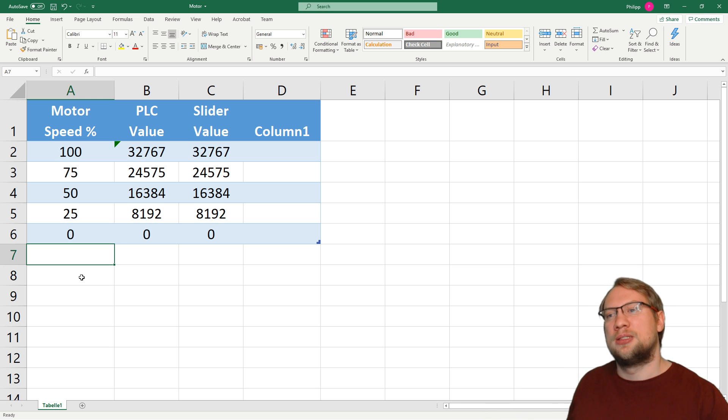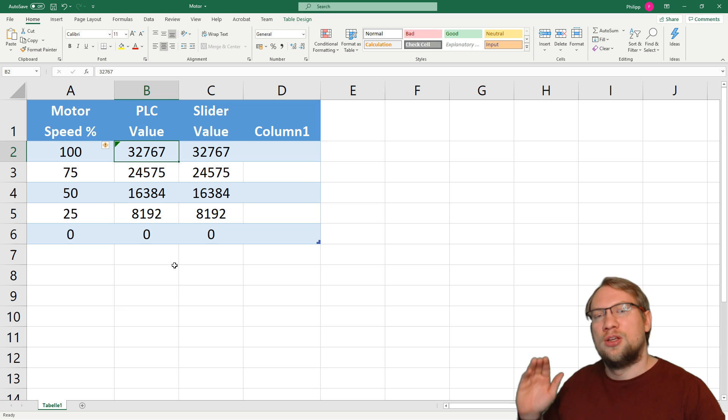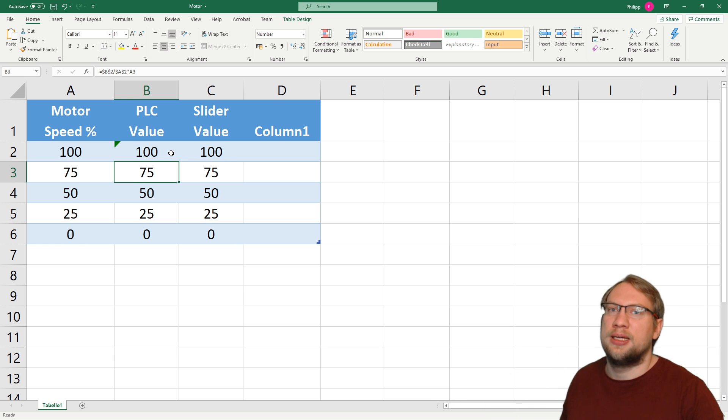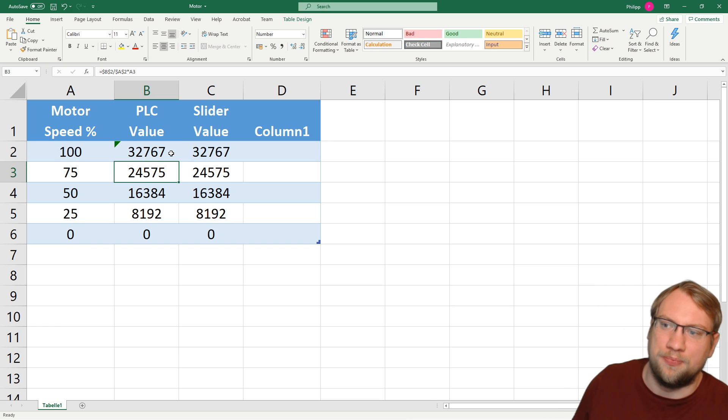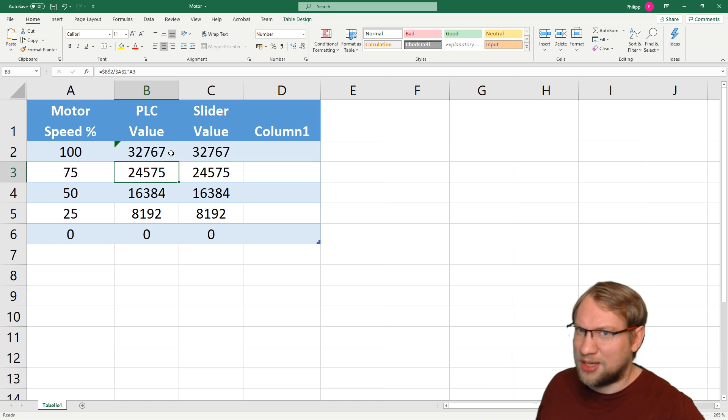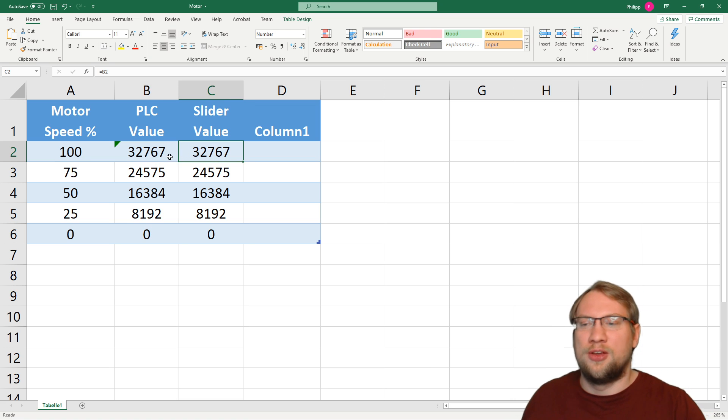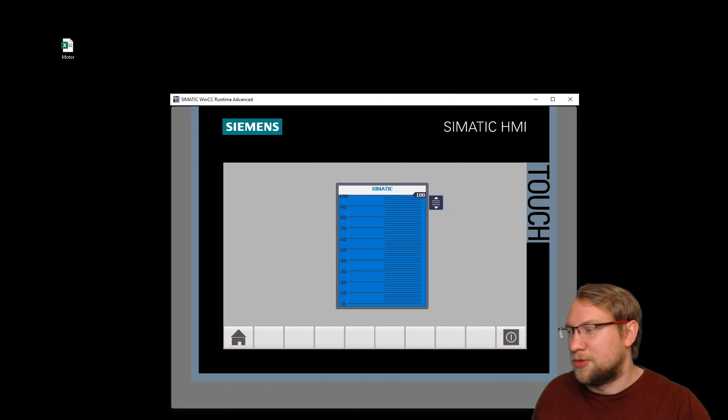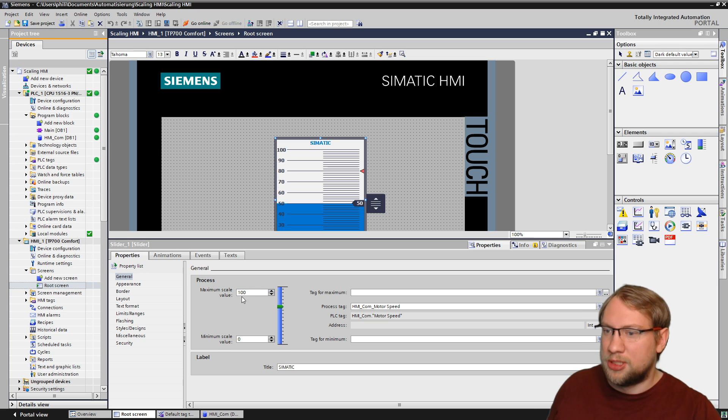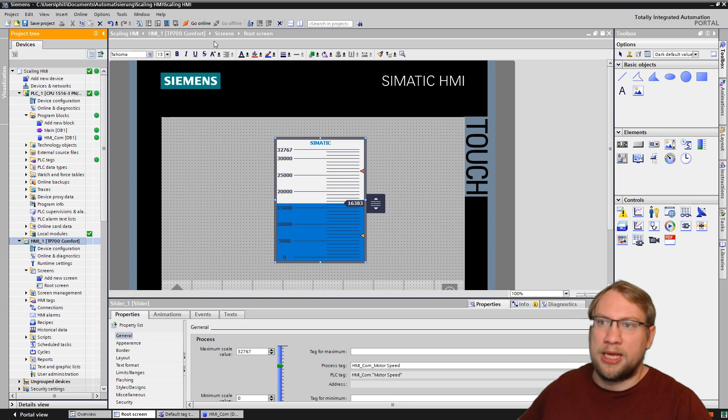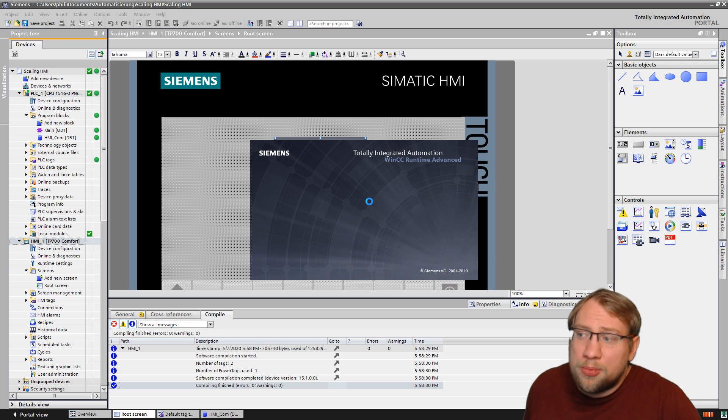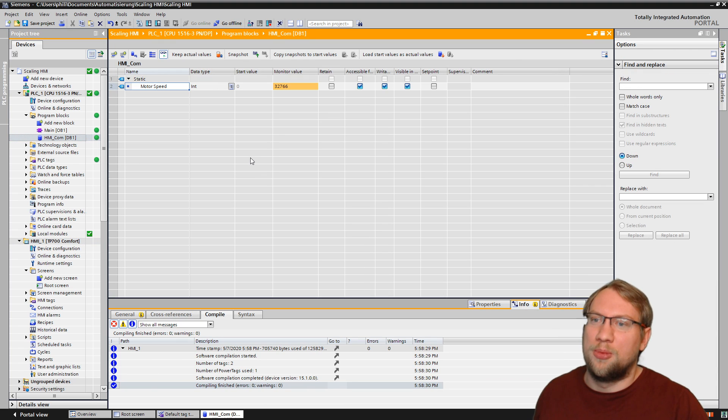Right now, if I want to go with a motor speed of 100%, what you would expect would be that my PLC value would also be 100. That is not the case. If it would be 100, everything would be perfectly fine. That is not the case. The PLC output, 100% of the PLC output is something around this value. That is just the output. It is also just this 32,000 something thingy. It does not matter right now. That is our maximum. So our slider, if I want to go to 100%, theoretically, we would need to put our slider also to 32,700 something. So let us do that. I can just go to my HMI, go here, grab this, and tell this in the properties, hey, the maximum value should be 32,700, boom.